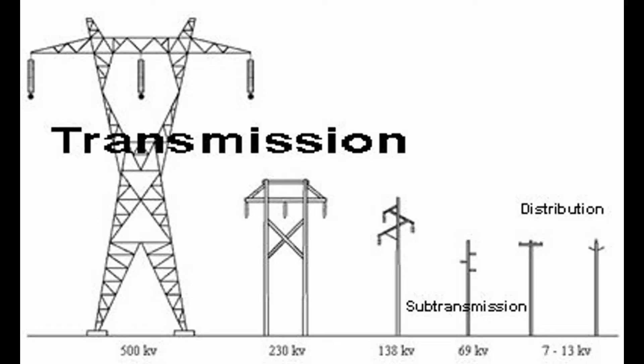When you see towers alongside the road, the really big one on the far left is 500 kV — that's your big-time long-distance power transfer. Next down is 230 kV; there's also a 345 kV in between. Then 138 kV or 115 kV in some places, then sub-transmission at 69 kV, then down into distribution levels at 7 to 13 kV — and those are normally on wooden poles, even the 69 kV lines a lot of times.